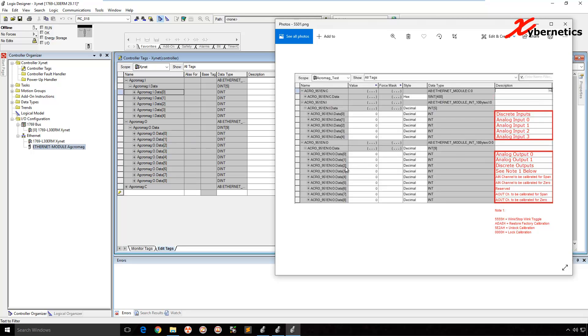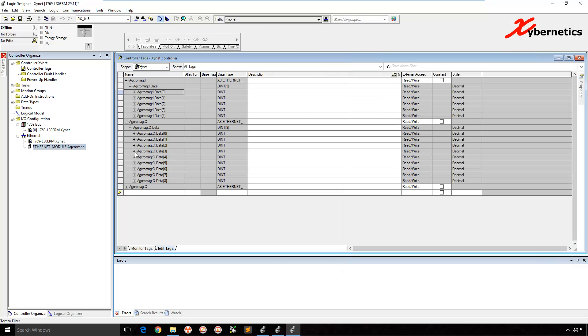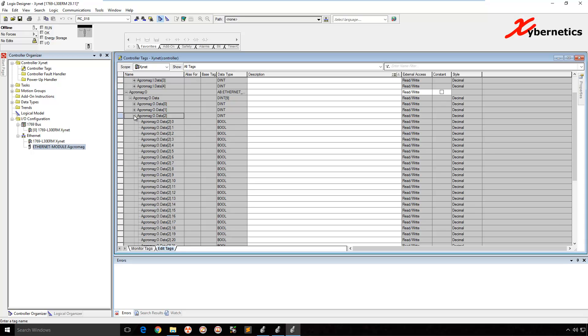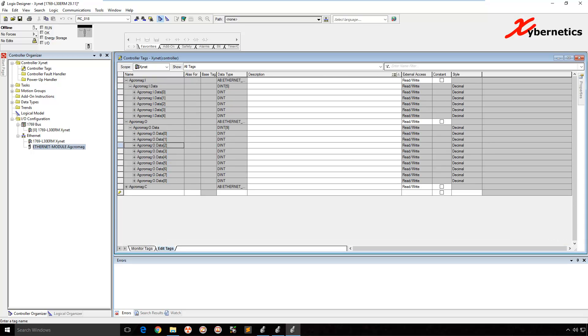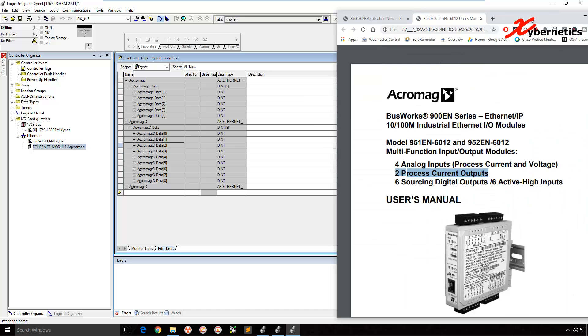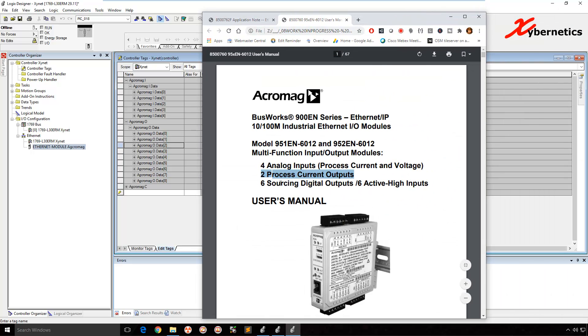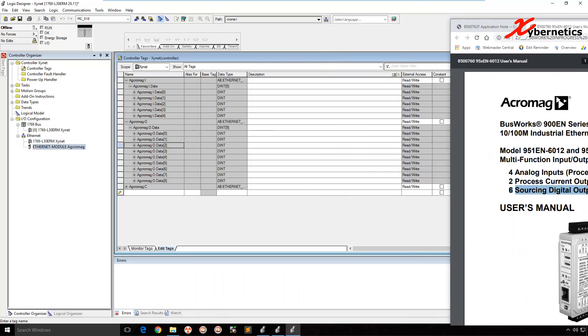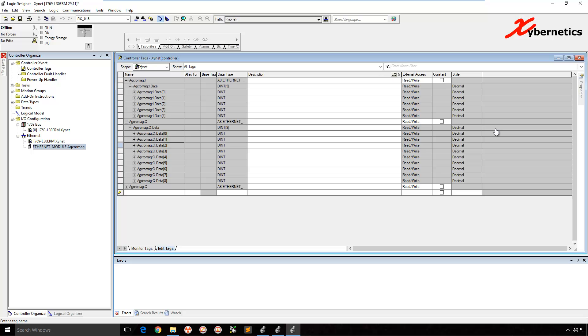Array element number two is your discrete output. Again, it goes from zero to 31 bits. The first, this is a six sourcing. So it's got six digital outputs. So the zero to five is what you're going to be writing to in order to output the value there.